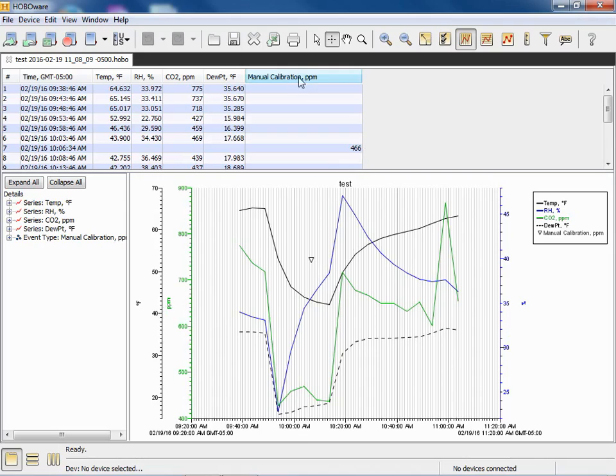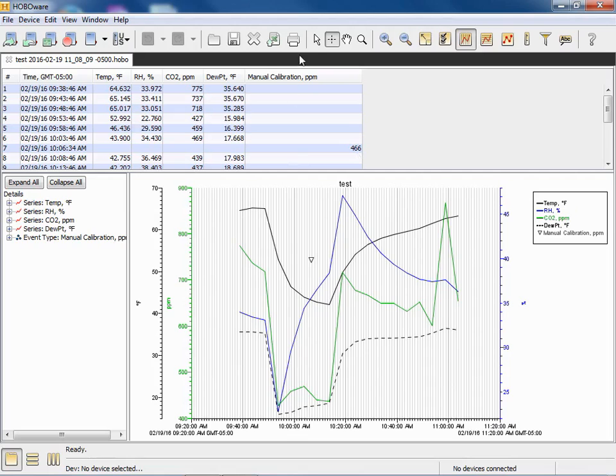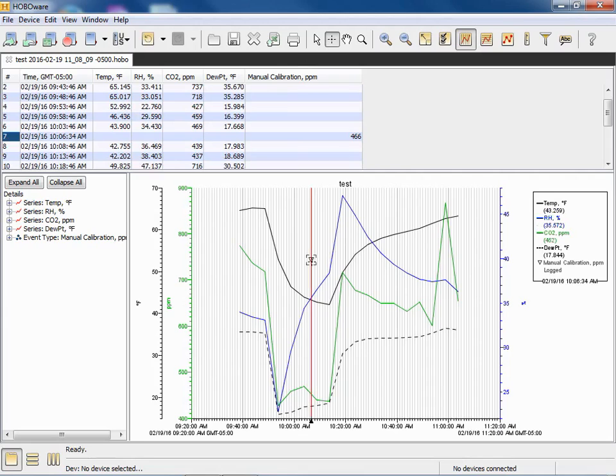You notice over here under the manual calibration series we have a manual calibration value that was recorded. That's what it's using to determine its offset to do its calibration. Using the crosshairs tool, if we click right on that, this is the internal event right here. Takes us right to that point. It was 10:06 AM this morning when we did that.